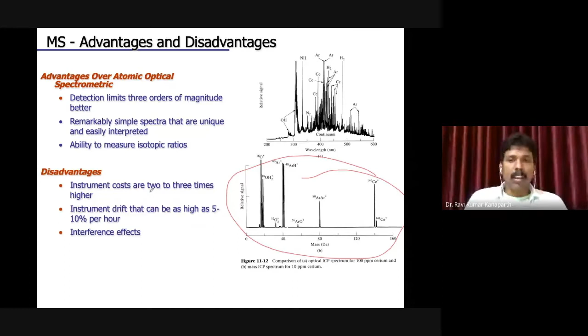And the bottom one, what you see here, is a mass spectrum of a sample. As you can see here, we have a limited number of peaks, therefore it is easy to interpret. At the same time, it has its own disadvantages. For example, the cost of the instruments is two to three orders higher. That is one problem. And sometimes instrument drifting, maintaining the vacuum inside the spectrometer, and interference effects are some of the major problems of mass spectrometry.